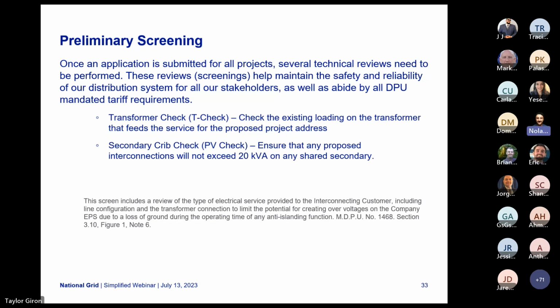The technical reviews maintain the safety and reliability of our distribution system for all of our stakeholders and must abide by all DPU mandated tariff requirements. The transformer check is one of the first technical reviews of a submitted project. The transformer currently feeding the existing site or nearest to the proposed system has several checks, including the DER would be once the proposed system is interconnected. And lastly, checking the existing load to avoid any potential interconnection issues.